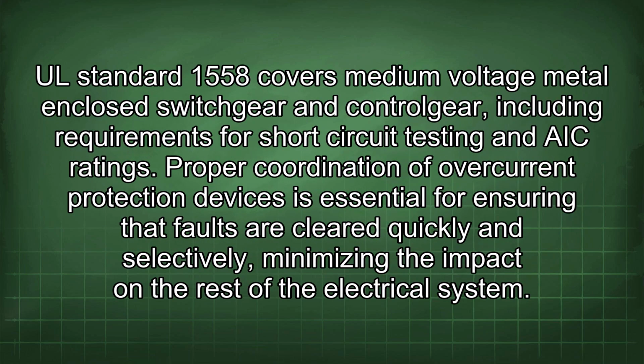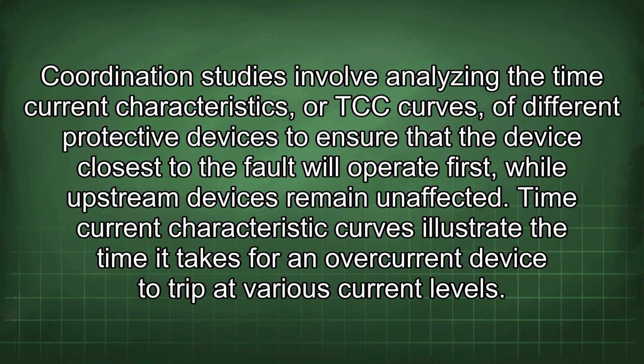UL Standard 1558 covers medium voltage metal enclosed switchgear and control gear, including requirements for short circuit testing and AIC ratings. Proper coordination of overcurrent protection devices is essential for ensuring that faults are cleared quickly and selectively, minimizing the impact on the rest of the electrical system. Coordination studies involve analyzing the time current characteristics, or TCC curves, of different protective devices to ensure that the device closest to the fault will operate first, while upstream devices remain unaffected.